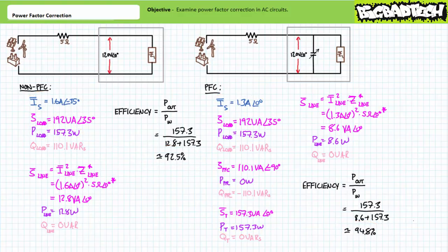Power factor correction is a necessary technique to the efficient management, generation, transmission, and use of power. More to the point, oftentimes industrial users of electricity pay dearly for systems with poor power factor, and as such, it's financially imperative that local systems appear to the utility as an electrical load with unity power factor. Unity power factor, by the way, means a power factor of 1. It is for this reason large factories might have their own means of power factor correcting the entire factory rather than individual loads. Conceptually, one might think of this factory scale power factor correction system as a bank of capacitors that are switched in and switched out as reactive power requirements internal to the factory ebb and flow. By the way, this simplification isn't that far from the truth.